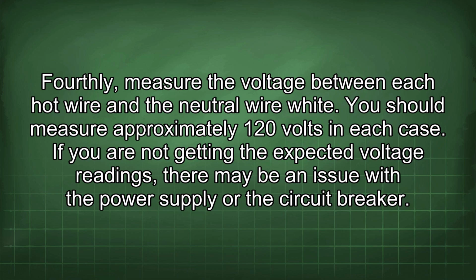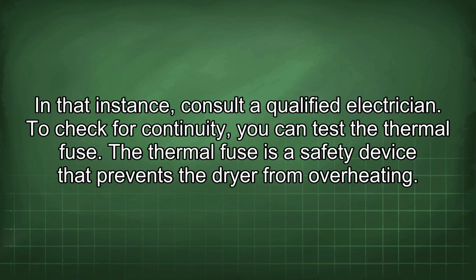Fourthly, measure the voltage between each hot wire and the neutral wire, white. You should measure approximately 120 volts in each case. If you are not getting the expected voltage readings, there may be an issue with the power supply or the circuit breaker. In that instance, consult a qualified electrician. To check for continuity, you can test the thermal fuse. The thermal fuse is a safety device that prevents the dryer from overheating.